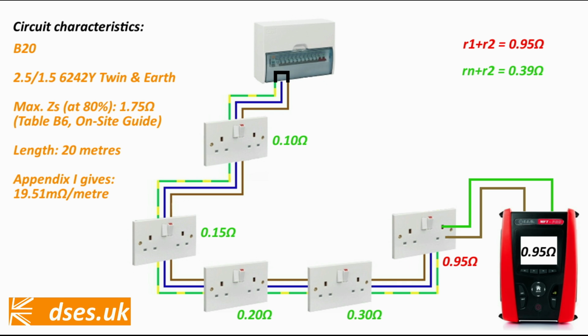The trouble is, we don't know for sure the route of that cable, and running a new cable or accessing where a junction or otherwise inaccessible point may be located may be wholly impractical. And this is where we need AFDDs to be non-mandatory. If I have a high reading that's nonetheless still within limits at this point, this is where I need to be able to say to the homeowner that I think I've identified a poor connection on this circuit that may go on to result in either a failure or high temperature arcing, which is of course a fire risk.